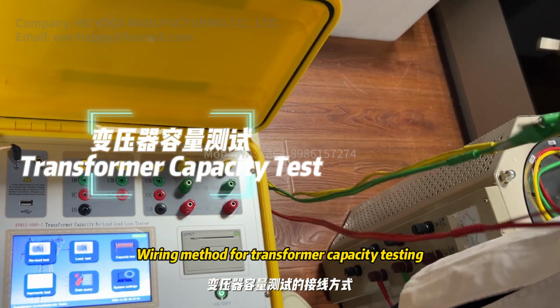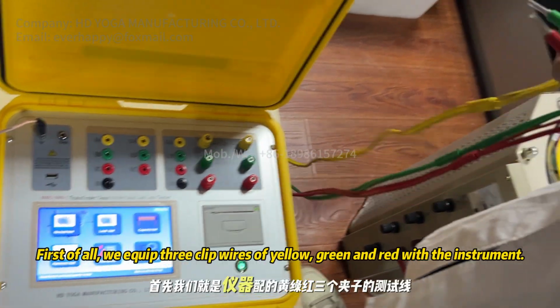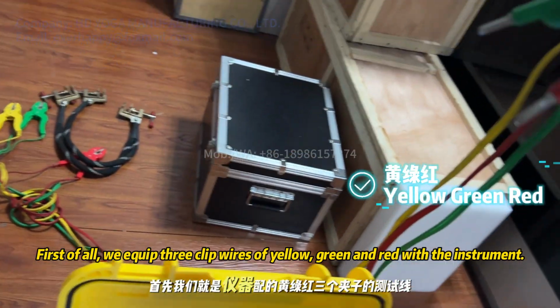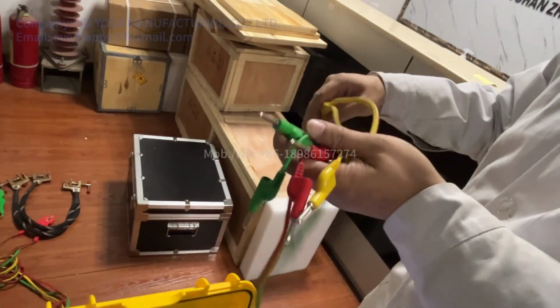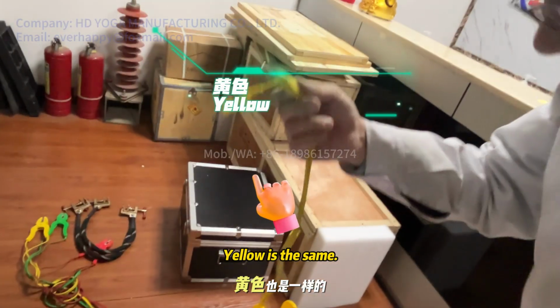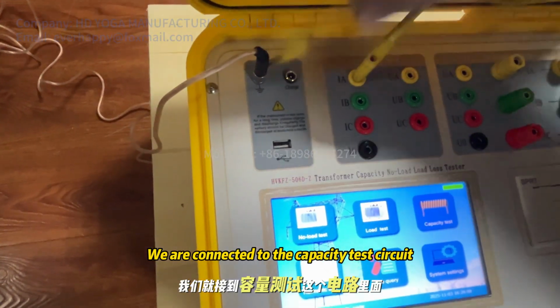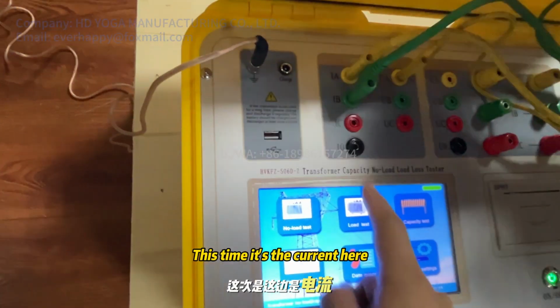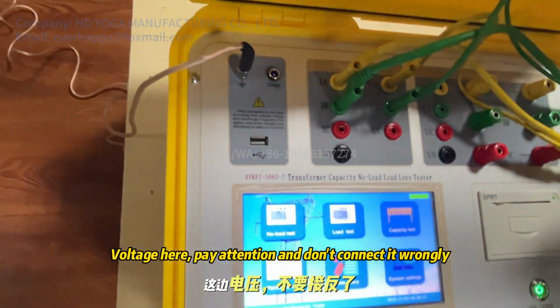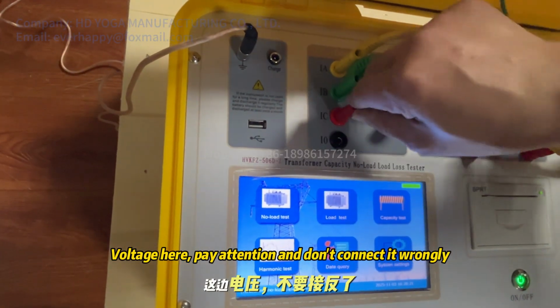Wiring method for transformer capacity testing. First of all, we equip three clip wires of yellow, green and red with the instrument. Yellow is the same. Crude connection current. Fine connection voltage. We are connected to the capacity test circuit. This time it's the current here, voltage here. Pay attention and don't connect it wrongly.